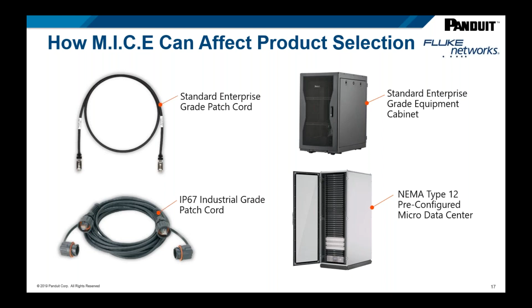As we look at the different solutions, we can match up the products we're using to the M.I.C.E. environment and to the different subsystem levels we're specifying for. At the higher levels of the network, we can use a typical standard grade, enterprise grade patch cord and standard enterprise grade equipment cabinet. But when we get onto the plant floor, closer to where the action is happening, we can have that same type of performance, but now with a sealed IP67 patch cord that can withstand the elements and is more robust and reliable. We can do the same thing for that cabinet, putting it in a NEMA enclosure that can be environmentally controlled and exist on the plant floor reliably.